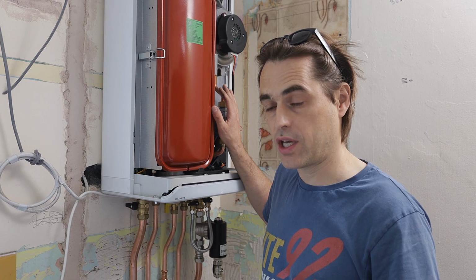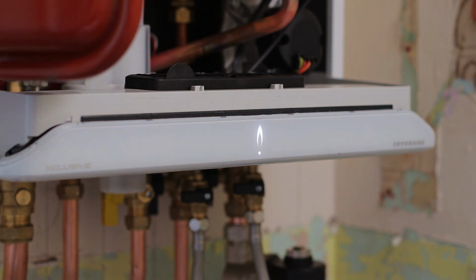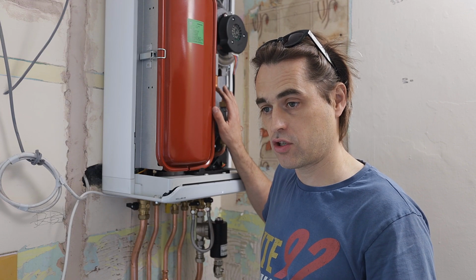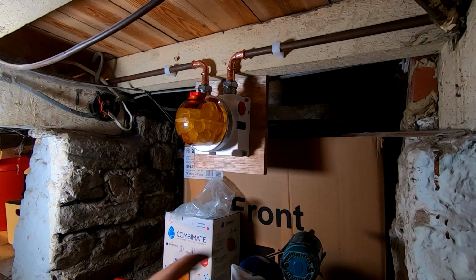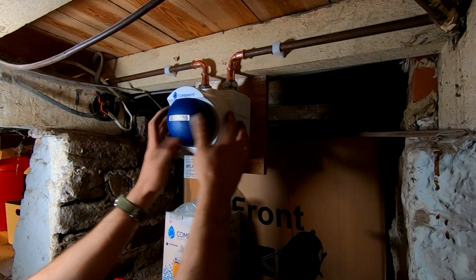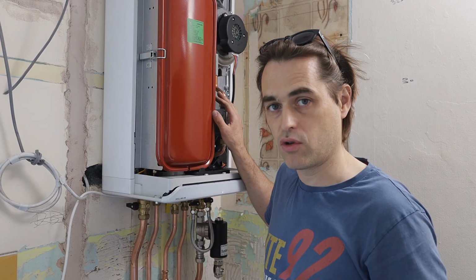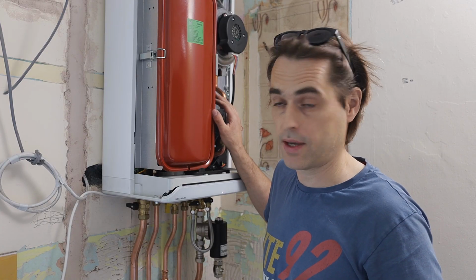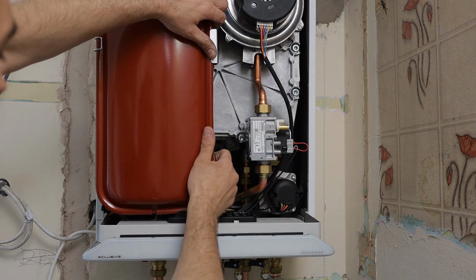The only drawback to this design is that this heat exchanger can scale much quicker in hard water areas as opposed to plate heat exchanger designs. So you always need robust scale protection, a full-blown water softener, which we're doing here, or at least a Combi Mate. Those watsits that you put on the pipe, they probably wouldn't do much, and I don't know if they do much anyway.